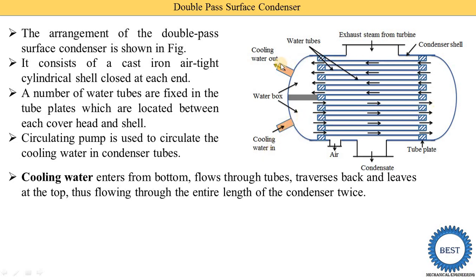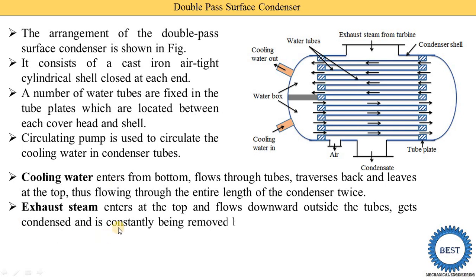Exhaust steam from the turbine enters at the top and flows downward, coming into contact with the tubes. Inside the tubes the water is flowing at a lower temperature, while the steam temperature is higher. Heat energy from the steam is transferred to the water, so the steam starts to condense and the water temperature increases. The condensed steam is collected at the bottom part of the condenser, and then the condensate is supplied to the boiler using a condensate pump.